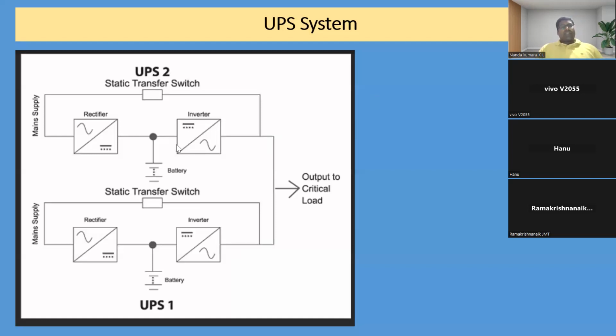In this configuration, in case any one UPS fails, imagine UPS one has some issue. In this scenario, if the rectifier has an issue, the UPS goes to battery mode. After some time the battery discharges, then this UPS goes off. That is the basic behavior, because in case of an inverter trip, it will not go to battery mode. It directly transfers the load to the other UPS. Here, if the rectifier fails, the battery drains, then the inverter goes off, then the load transfers to the other UPS, which takes care of it.